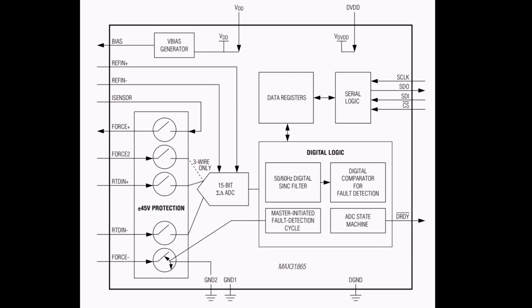The voltage across the reference resistor is then used as the reference voltage for the ADC, while the voltage across the RTD is applied to the RTD's differential inputs. The ADC then produces an output equal to the ratio of the RTD resistance to the reference resistance. It's quite simple really.